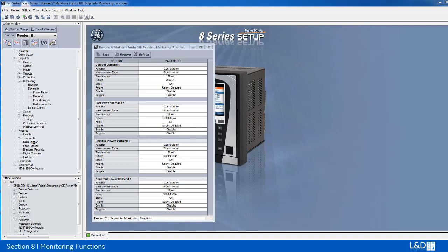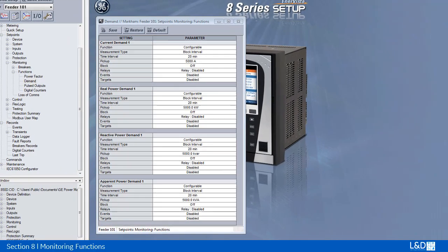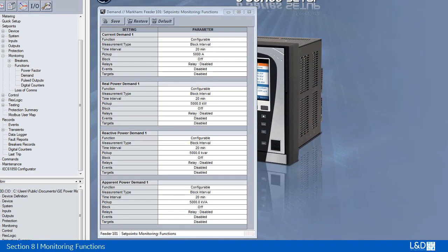Current demand is measured on each phase and on 3 phases for real, reactive power, and apparent power. Set points allow emulation of some common electrical utility demand measurement technique for statistic or control purposes. The relay can be set to calculate demand by any of 3 methods.